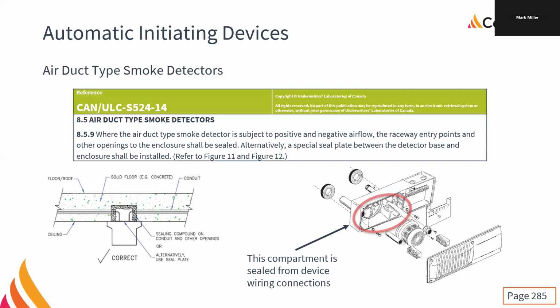If we have the cover off of this thing or not screwed down properly, we're not going to get proper airflow and it's not going to work properly. And one of the things we have to do for verification to make sure it's actually working properly is we have to open the unit up while the air handling unit is running, and we have to do a pressure test. We use a manometer to make sure that we have a proper differential pressure between the intake and the exhaust tubes, and that it's not too high or too low. So it can be a little bit annoying to work with.